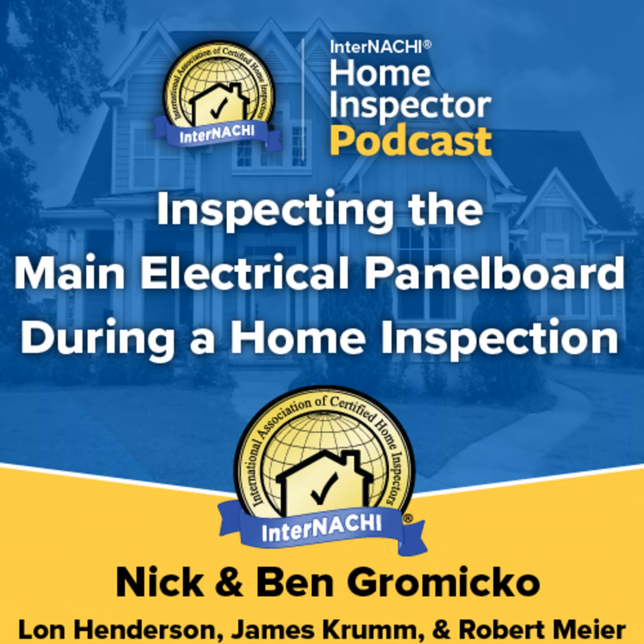Panel board basics. Let's learn about the basic components of a panel board, including service entrance conductors, main lugs, main disconnect, branch circuits, hot bus bars, neutral bus bars, and ground bars. For a commonly installed 200 amp service, the SEU service entrance cable between the meter base and the main electrical panel board will have 2 4-aught aluminum conductors for the hots and a bare 2-aught aluminum ground or neutral conductor. The main lugs or terminals are the main connection point between incoming electricity and the panel that distributes the power to the house.